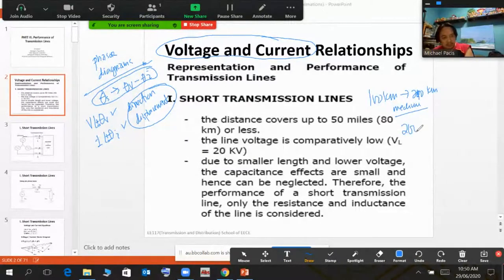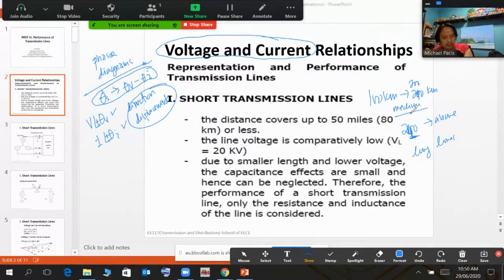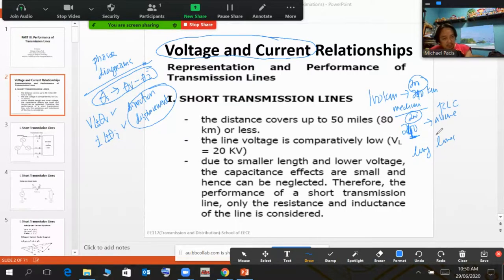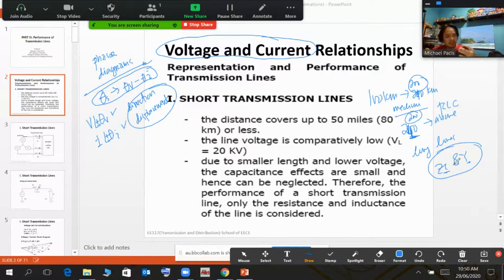There is another type of line — 200 kilometers and above is considered a long line. Some references use 200 km and others use 240 km as the boundary, but anything above that is a long line. We will stick to 240 km for medium and above 240 km for long. The medium line has RLC parameters, while the long line uses ZL and admittance — considering conductance, resistance, L, and C — so all line parameters are considered for the long line.